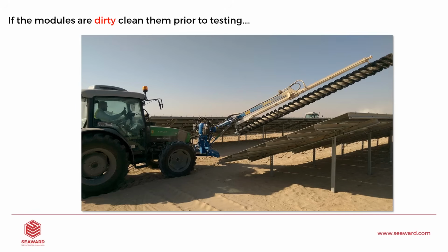But really, if you get to the site and the panels are dirty, you should really ask for them to be cleaned. If they can't be cleaned and the client insists that you carry on testing, we need to take that into our STC calculation, our standard test condition calculation, and we need to put a factor in there for soiling. And our software will allow that. But also, we're not going to get good results when the panels are dirty. Basically, it amounts to shading of the panels, and that's going to drop our short circuit current down, and it's not going to give us a good idea of where we're at.